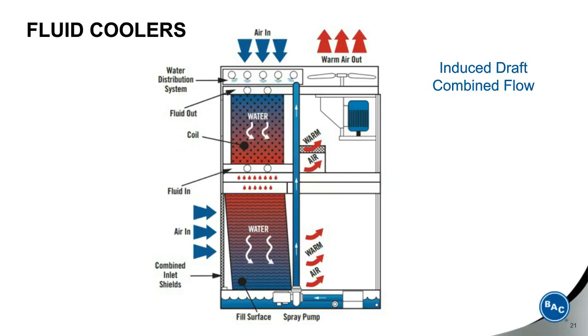Another type of cooling tower that's been introduced in the past few years is known as induced draft combined flow designs. This is where the coil, which you see is located at the top of the unit, has water sprayed over it, and air also is brought down over the coil surface. The spray water picks up heat and then falls off the bottom of the coil onto a fill deck, which is the same as what could be used in an open circuit cooling tower. And that water is then subcooled below the temperature that can be achievable without the fill deck.